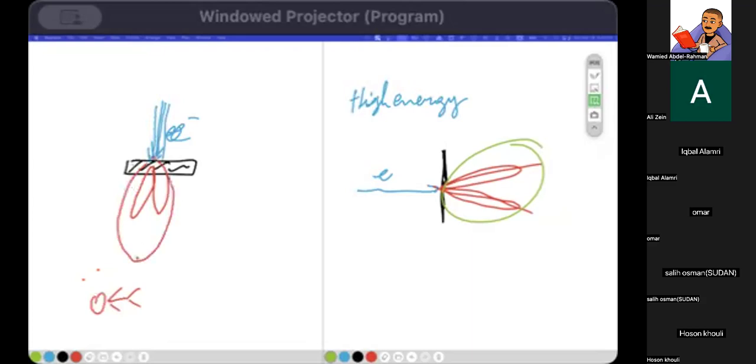We will actually have something in this 0 direction because some electrons could be hitting the target at an off distance and so on. But the bottom line is that this is an efficient way of utilizing the megavoltage X-rays produced by a LINAC. This represents what we drew before for an X-ray tube, whereas here this is the Bremsstrahlung produced from a linear accelerator.